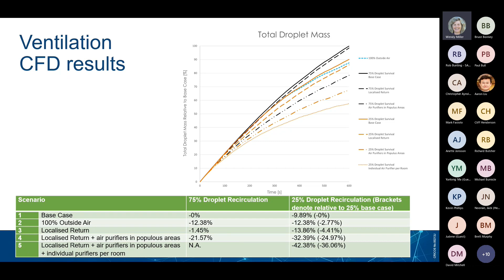So what does this mean? The key findings at this stage seem to be, well, a number of things. Firstly, increasing the outside air percentage poses significant challenges to the operation of hospitals. First of all, it triggers increasing cooling and heating loads and energy consumption. Secondly, ductwork and coil capacities, depending on the layout of the HVAC system, might not be appropriately sized to enable 100% outdoor air without a significant upgrade. And the capital and operational costs of either the upgrade or the increased energy consumption seem to be at odds with the sustainability objectives.